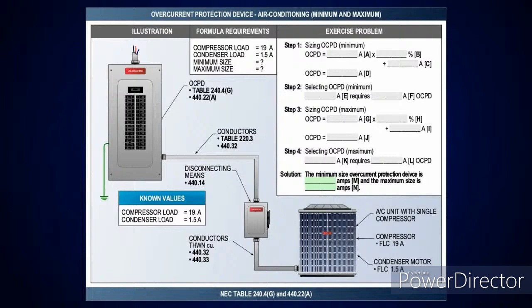Sure. And one other thing I want to point out is some will say, why didn't you go over and use the tables in 430.247 through 250? The reason is because this is an assembly. All right. So it's one unit, and therefore you're going to use the nameplate value that's on there. Okay.